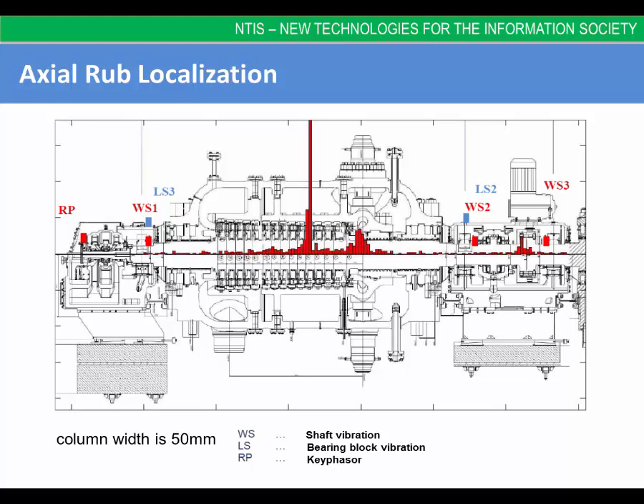As already mentioned, the RAMS is able to localize the place of contact. This example shows rubbing localization in the high pressure part of a 220 MW steam turbine. The symptoms of shaft and blade rubbing were successfully detected and measured by the RAMS monitoring system during steam turbine operation in the year 2012. The symptoms were significant and simultaneously detected in three measured planes, and consequently the rubbing origin localization was performed.